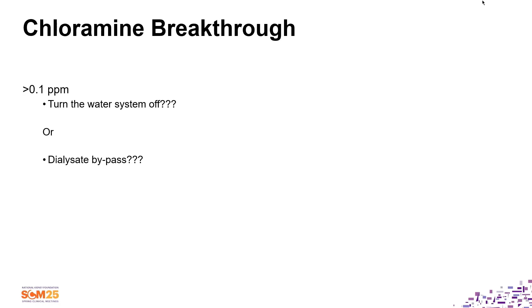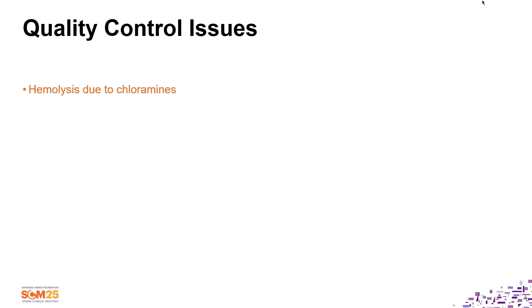Quality control. And quality control is now part of their survey mechanism. They say, show me your quality control for the strips. So facilities weren't doing it. They were taking it for granted. They opened up the bottle, it's good. But it was not. And so that event happened. Okay. And hemolysis due to chloramines. The wrong test got used for free chlorine tests.